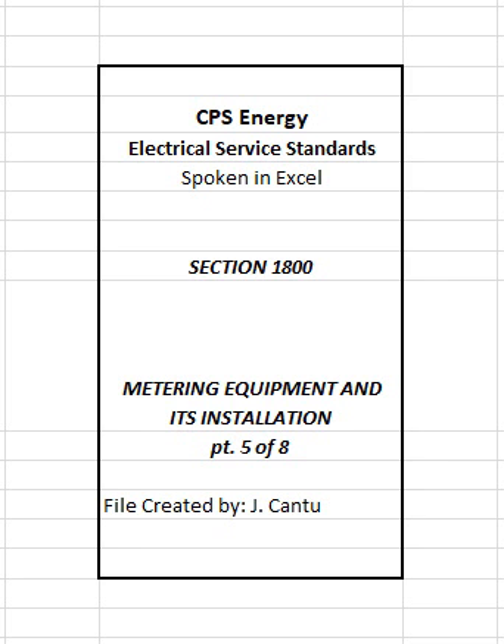5. Extending into narrow alleys or adjoining property, unless an easement is obtained. 6. Areas accessible only through trapdoors or hatches. 7. Areas accessible only by ladder. 8. On CPS Energy poles, except overhead primary meters. 9. On portable buildings or on manufactured homes or portable/temporary structures, refer to definition of portable. 10. Areas that expose personnel and/or metering equipment to potentially hazardous conditions.